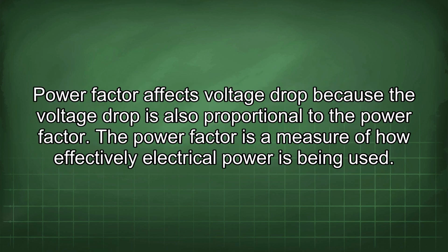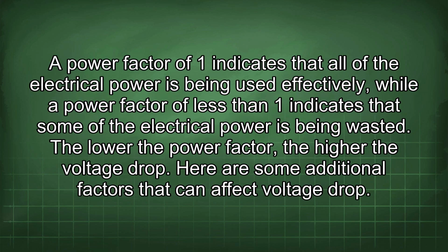Power factor affects voltage drop because the voltage drop is also proportional to the power factor. The power factor is a measure of how effectively electrical power is being used. A power factor of 1 indicates that all of the electrical power is being used effectively, while a power factor of less than 1 indicates that some of the electrical power is being wasted. The lower the power factor, the higher the voltage drop.